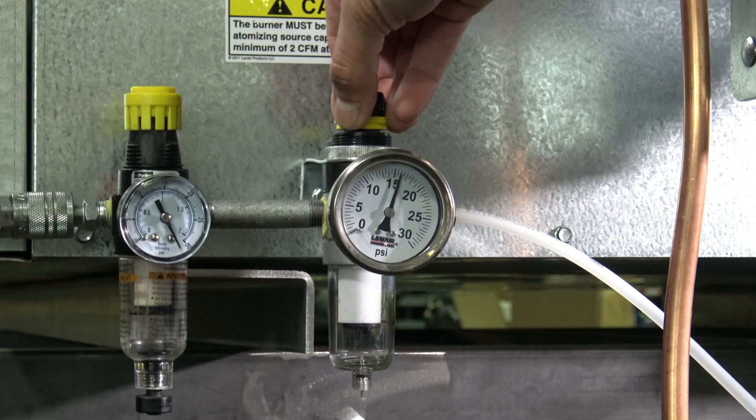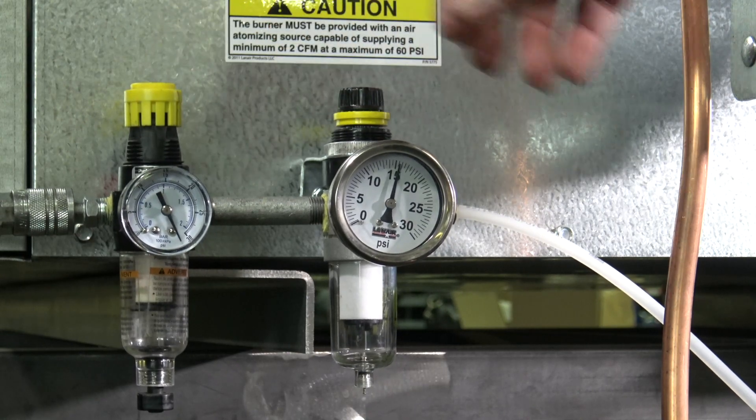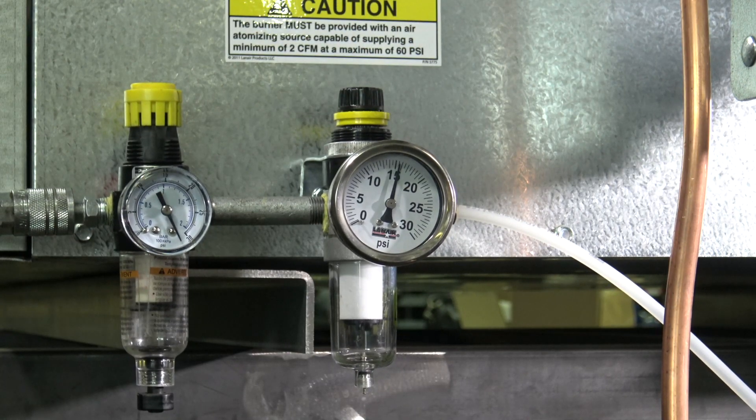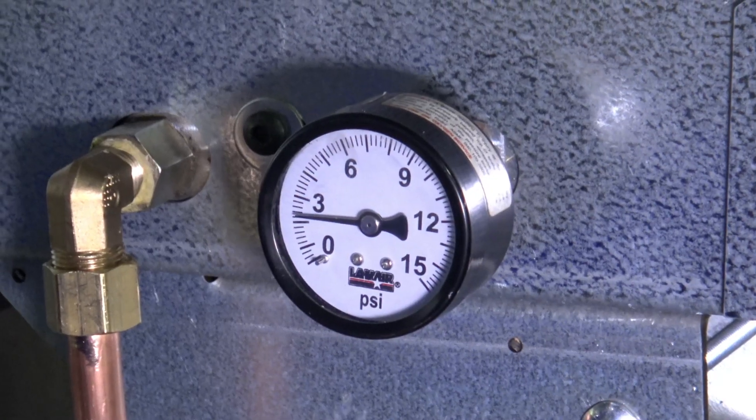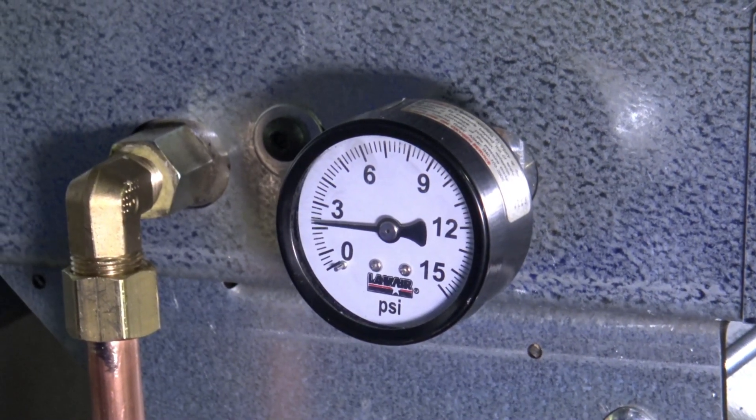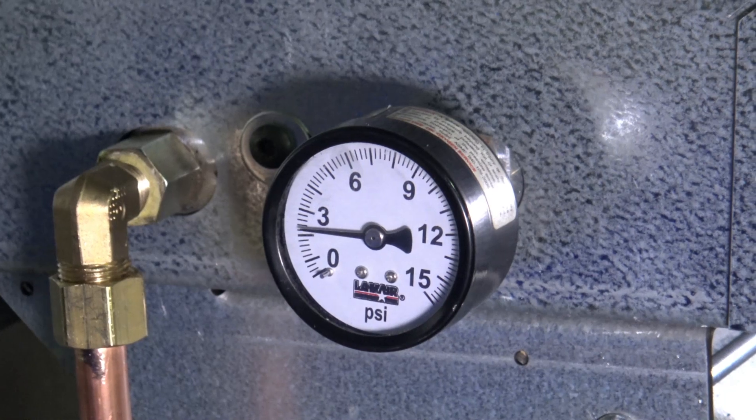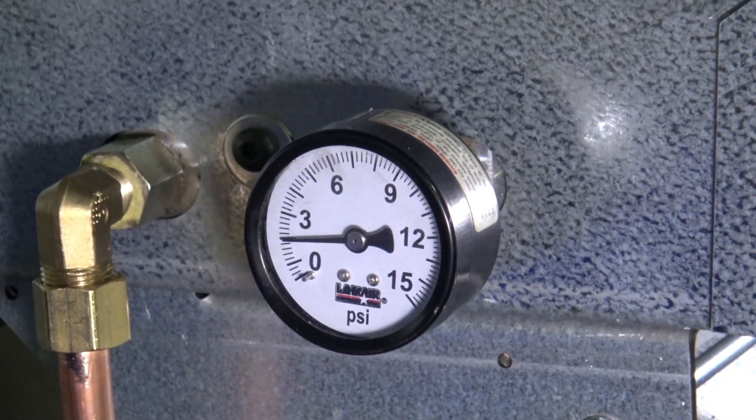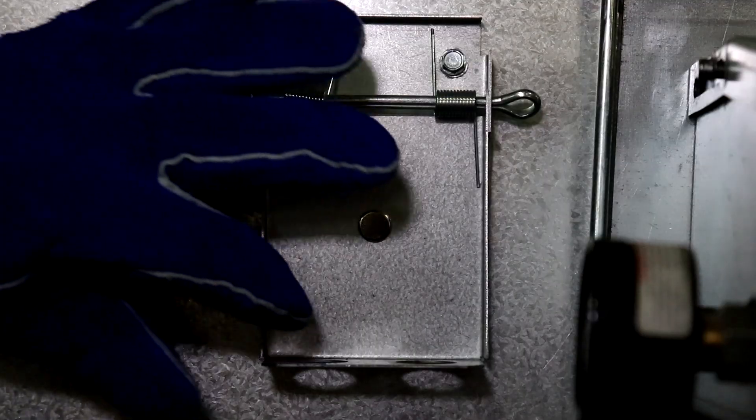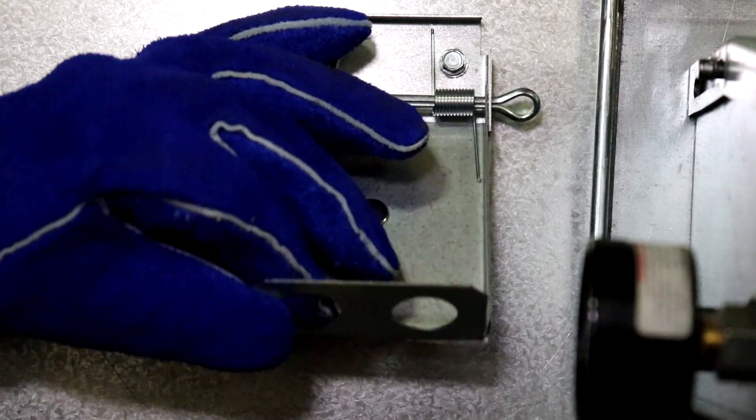Periodically inspect the air pressure regulators to ensure that they are free of moisture and debris, as these contaminants will cause a malfunction of or damage to the unit. Next, ensure that the appropriate air pressure is being delivered to the burner, based on the product instruction manual's recommendation for your model. Once these initial settings have been confirmed, use a gloved hand to open the flame inspection port cover of the heater cabinet, and visually inspect the flame.